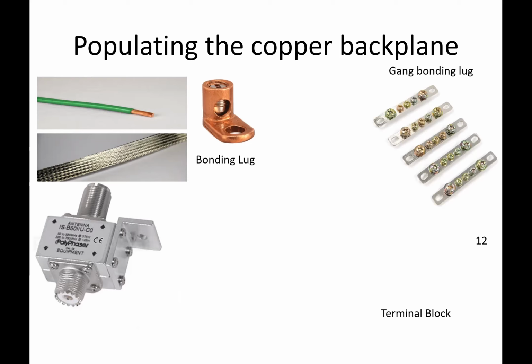Also in this picture, you have what we call a gang bonding lug, or just a gang lug. It's a way of using one lug that's got 5 screws on it. You bond that to your backplane using fasteners. Now all of a sudden you've got the ability to use 5 fasteners to install your copper wire or your braided wire to the grounding plate that's inside your service panel.